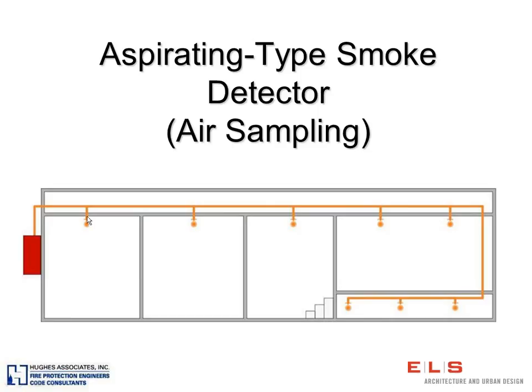And this looks really large, but it's a teeny, tiny little opening, just a hole, a port that would come through the ceiling. So if you're standing down here on the floor, you would look up and would not even be able to see that hole in the ceiling, particularly if you have a painted ceiling or some other architectural element that is very important for the character-defining features of the building. And I'm sure that if Kurt was speaking now, he could be a lot more articulate about what you might find on the ceiling in your building. And over here, we can also use an air sampling type smoke detection system if we have any underfloor spaces, like you would see in computer rooms, or other applications where you could have an underfloor space that would require protection.